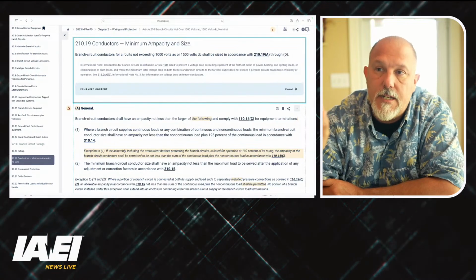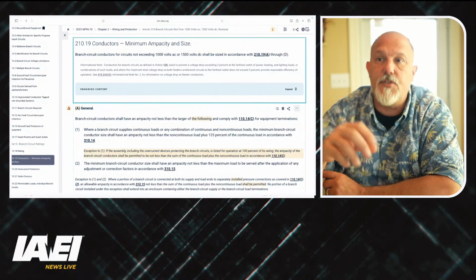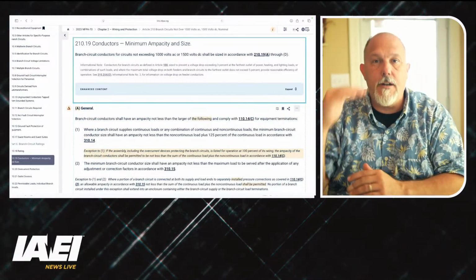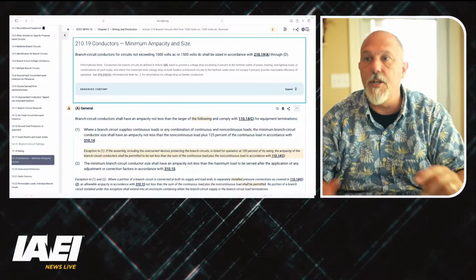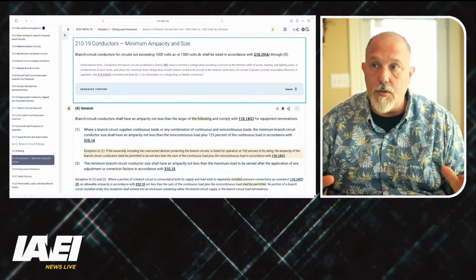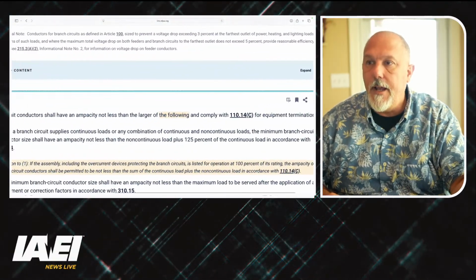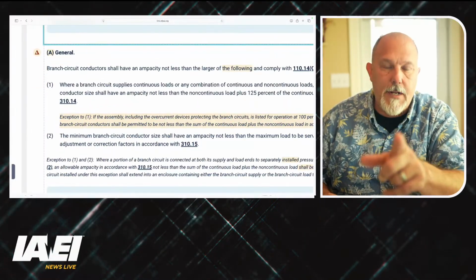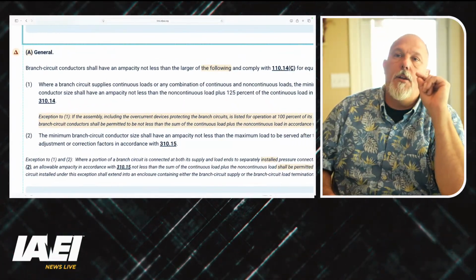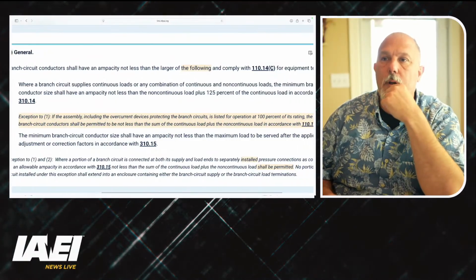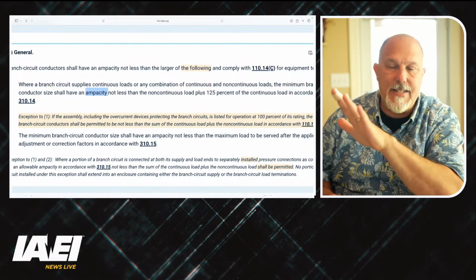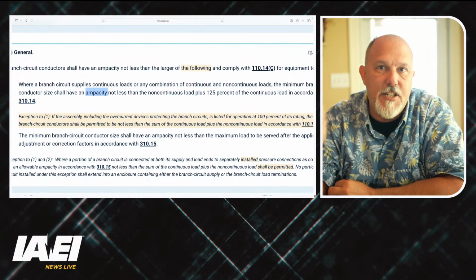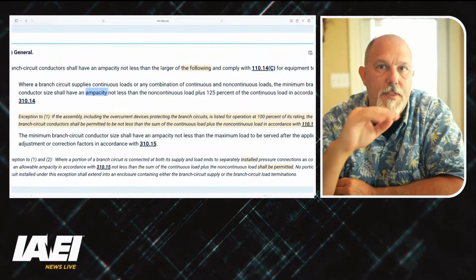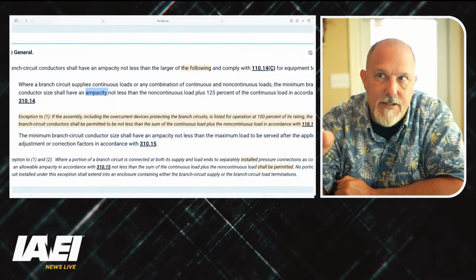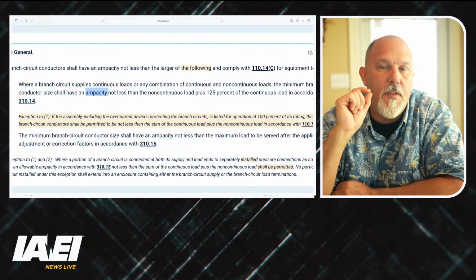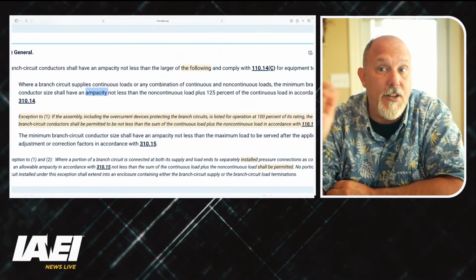A1 tells us to focus on the equipment. This is continuous and non-continuous. 125% of the continuous plus the non-continuous. You do not consider conditions of use. And we had someone who commented, and I believe rightfully so, and remember I told you during Code Panel 2, this cycle, we had somebody who wanted to remove the word ampacity because we're not talking about conditions of use in A1. It has nothing to do with ampacity at all. This has everything to do with the equipment and 80% rated equipment.